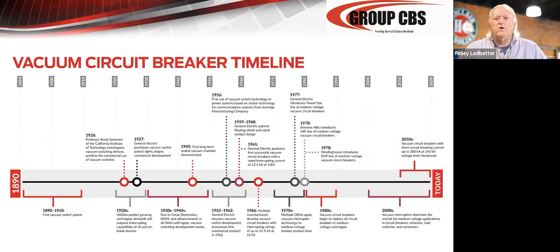Basically, a radial and axial magnetic field design. The Europeans with an axial field, Westinghouse with a radial field. GE adopted the Westinghouse patent for the radial field, and most of the Europeans are axial field. But either one does the same thing. It causes the arc roots to dance, or to move across the contact surface, instead of staying fixed in one place and gouging a hole through the contact. And that was really the breakthrough. That, and materials that they were able to outgas, getting the gases out of the materials so the materials themselves did not contaminate the inside of the enclosure.